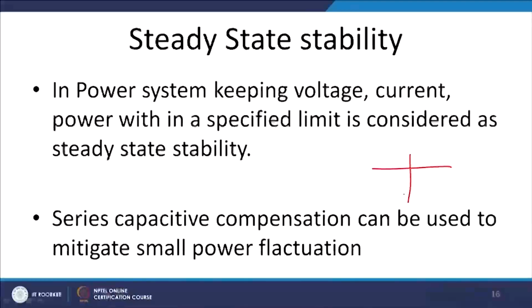For stability, we need to maintain the voltage, current and power at normal operating conditions. If all of a sudden a disturbance or sudden sag occurs, let us say a transmission line touches a tree, then every 10 or 20 milliseconds you get a voltage sag. In that condition, series injection can actively mitigate that sag. For example, series capacitor compensation can be used to mitigate small power fluctuations.